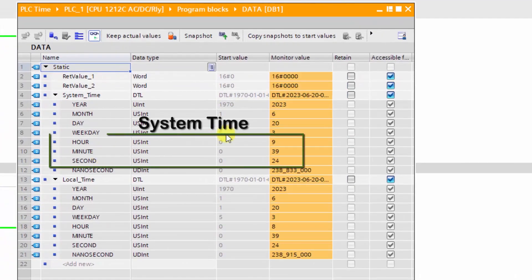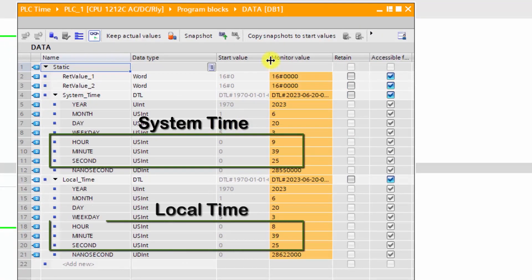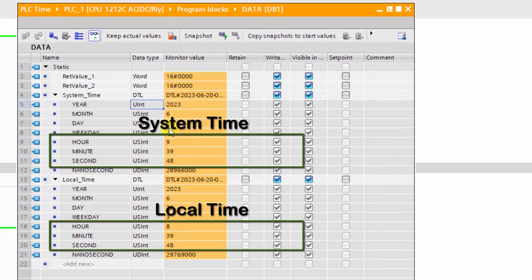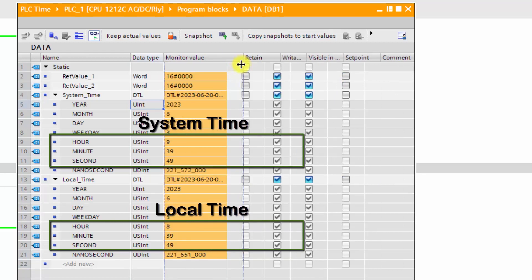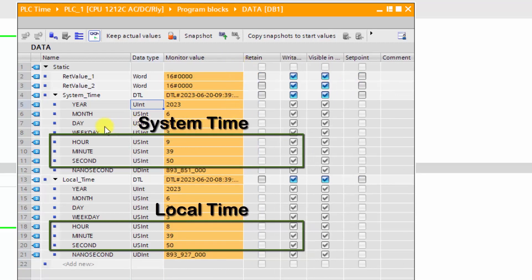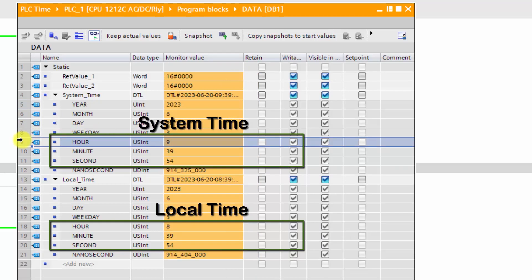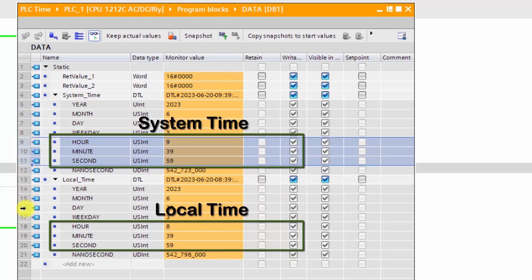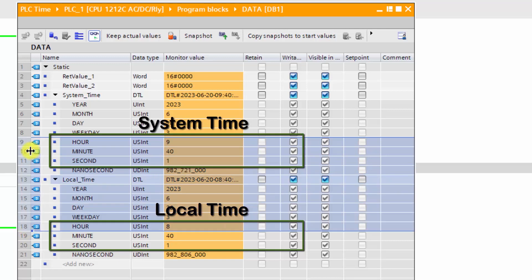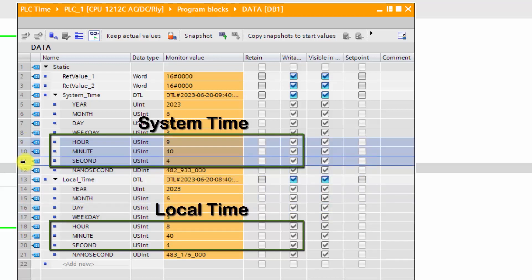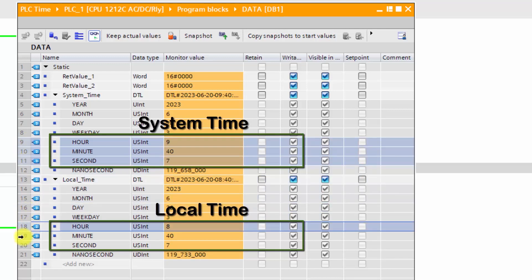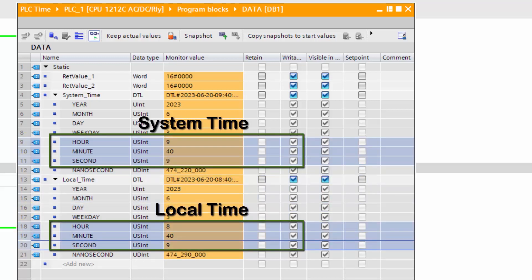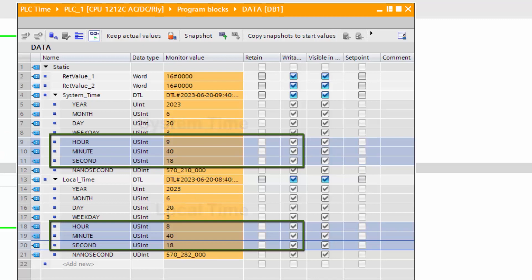We enter online with the data block. We can see that the system time and the local time are different, and both are different from the actual time right now, which is 10 o'clock 39 minutes. It's still weird, isn't it? By going back to the online menu and checking the PLC internal time, we can ensure that the three types of time are different.